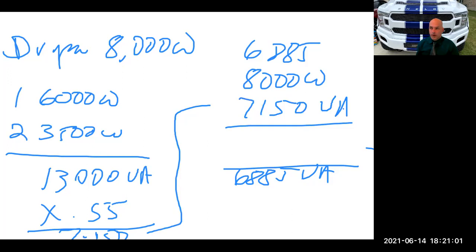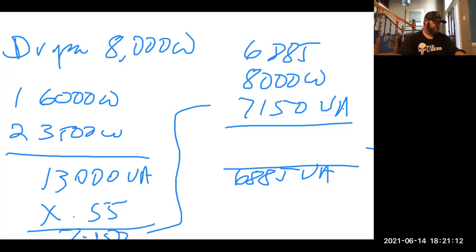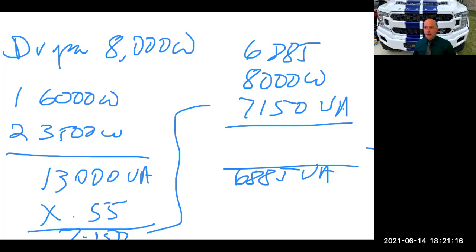So just remember, you will have to take the derating step for the lights and plugs. After you had the 4,500, you do include the 4,500 in that first step, so they do get derated. That's sometimes easy to forget and try to not derate it, but that gets derated. And then Note 4 is only for branch, not for services. So no adding anything.